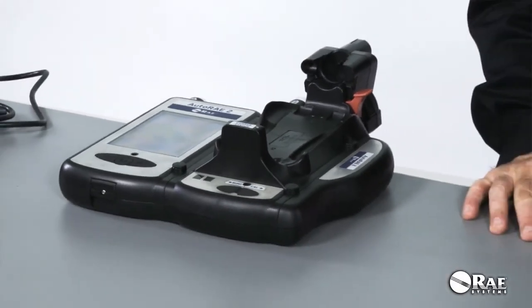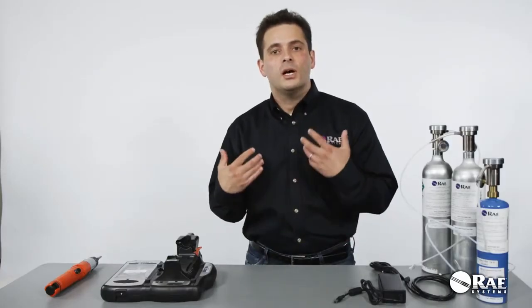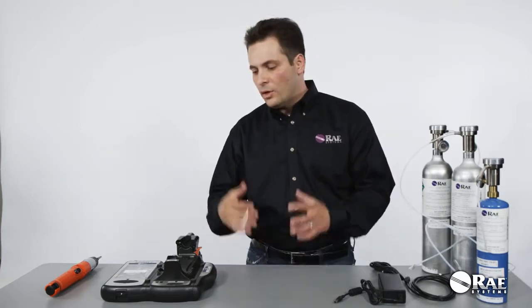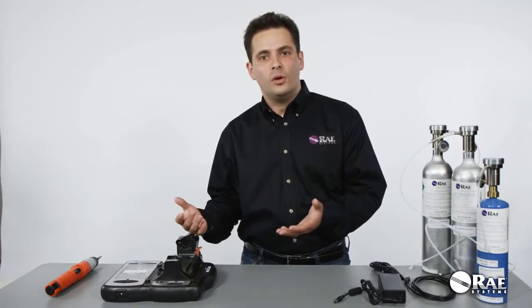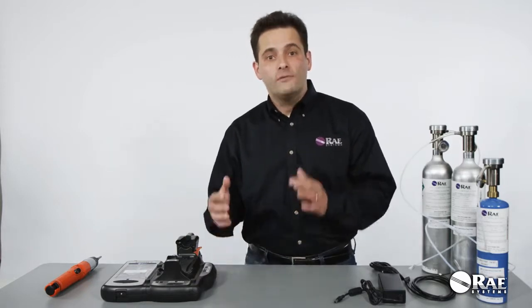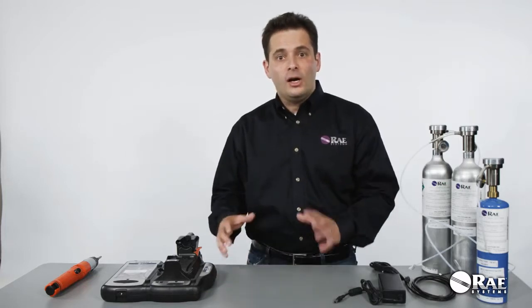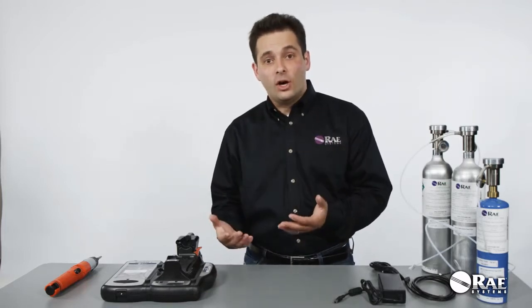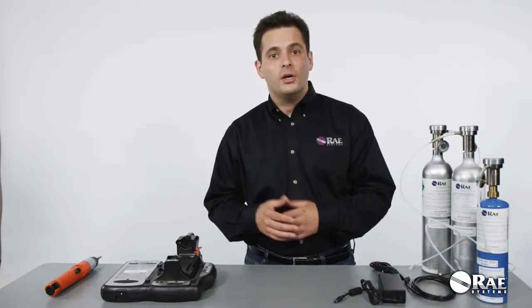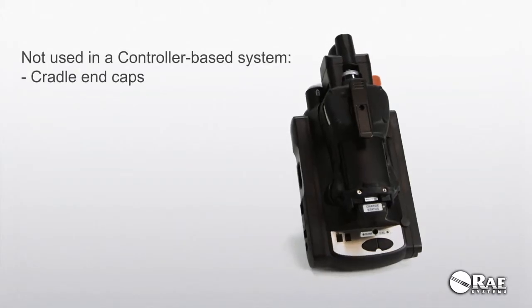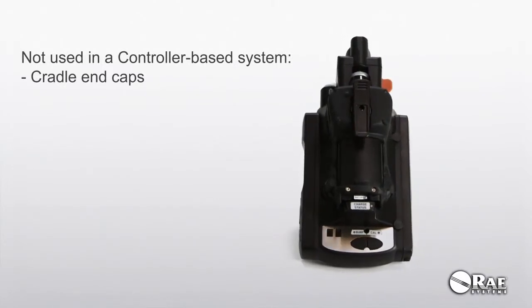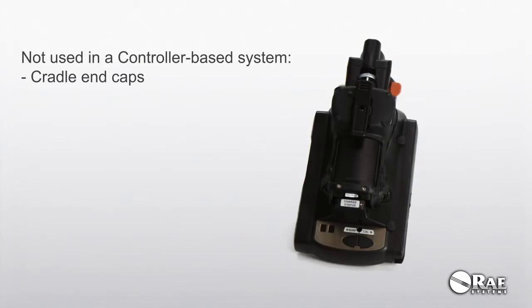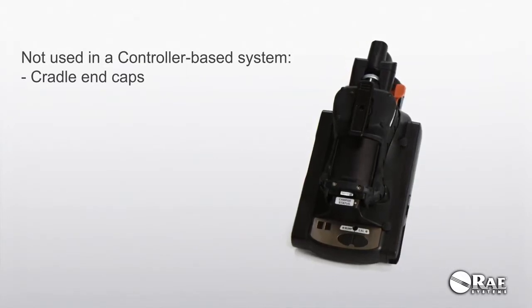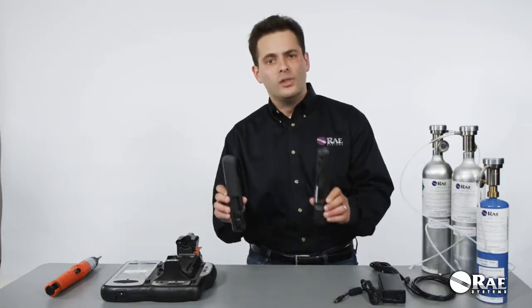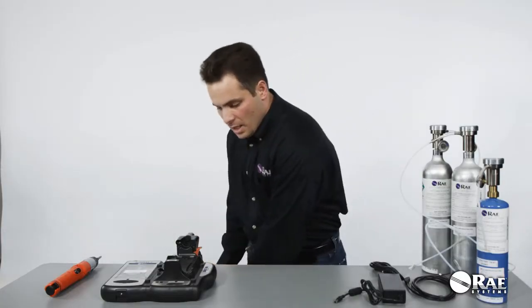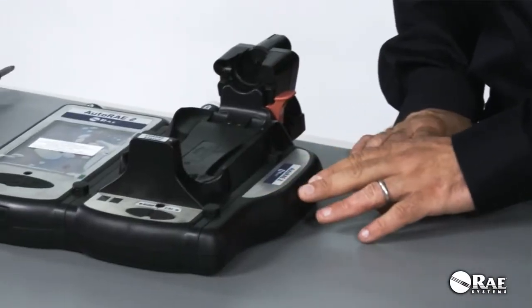I would like to mention a couple of things to keep in mind in regard to how the system is shipped to you. The system comes with a controller and the terminal adapter in one box, and each cradle in its own individual box. So there are a couple of things that come with the cradle that are not used when the cradle is deployed with the controller. Those things include the 2 end caps. These end caps are only used if the cradle is deployed in stand-alone mode or without the controller. If the cradle is deployed with the controller, they're not used, and the terminal adapter is used instead.